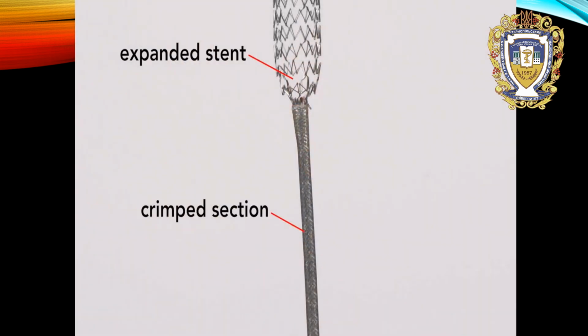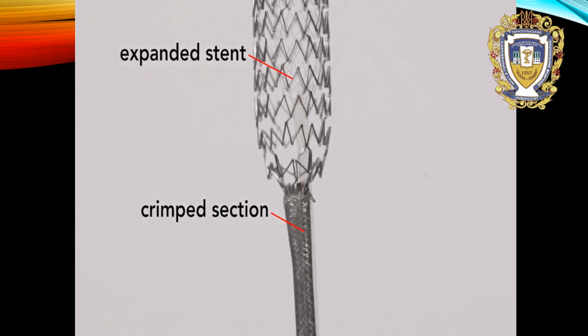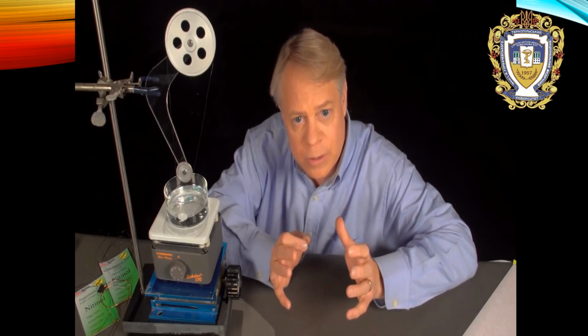To use it, a cardiologist chooses a stent with a slightly larger diameter than the vessel wall. It's then crimped to a size smaller than the vessel, inserted, and allowed to expand. Because it's larger than the vessel's diameter, it keeps a force on the wall and resists compression.